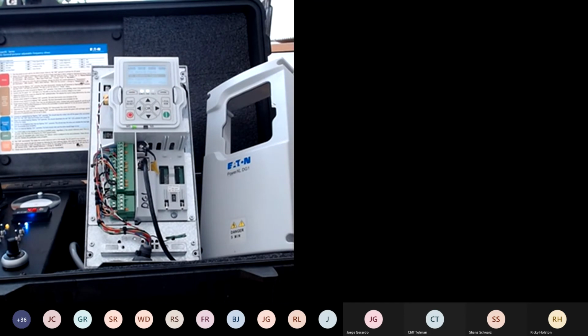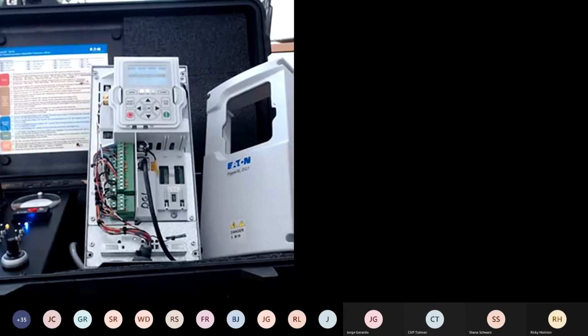And then again, the speed control is very straightforward. We can actually use also a valve. So let's say if you do have some valve control parameters, you can program through either your PLC or your drive: open valve, start drive, close valve, safety, and shut down at the drive. So there's obviously many different ways we can address programming in the field. It's a very neat application because of the flexibility. We have so many ways we can customize to your needs. And again, VFD does have some PLC multi-motor capabilities and a lot of extra benefits here that we can use without having to go into a full-blown system.